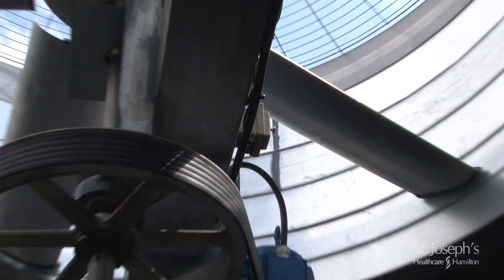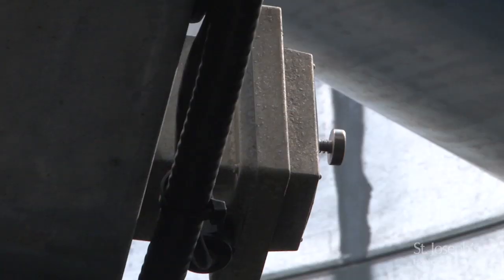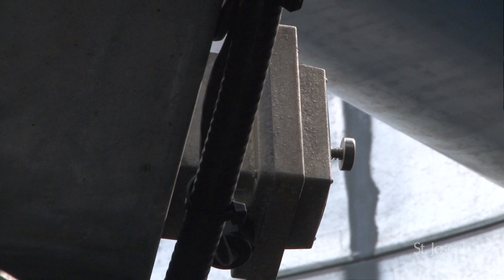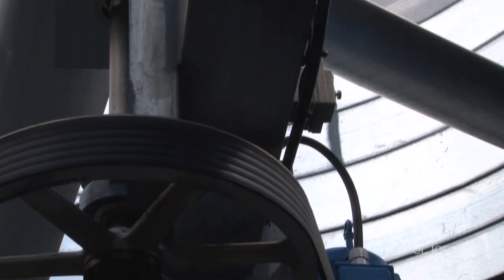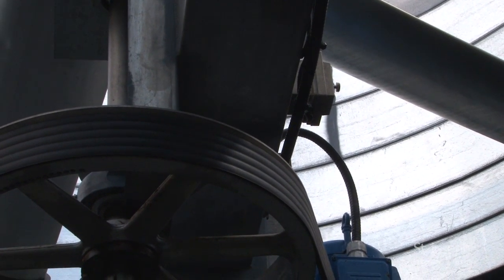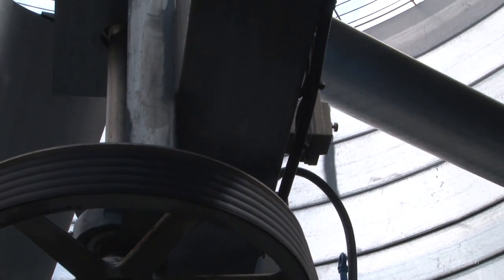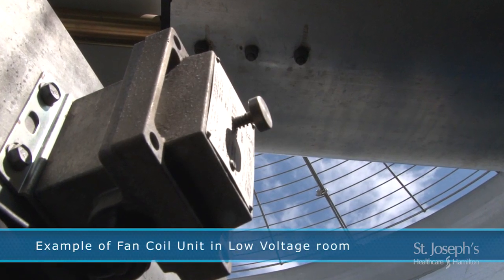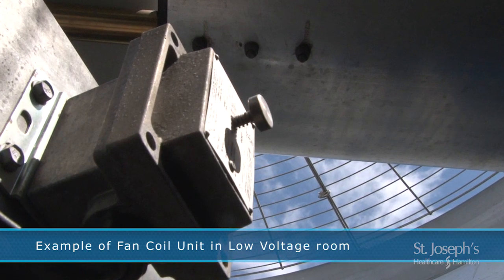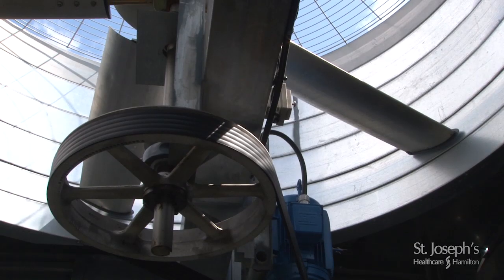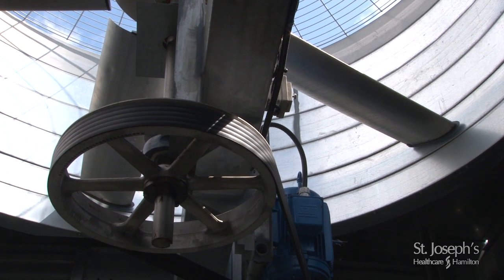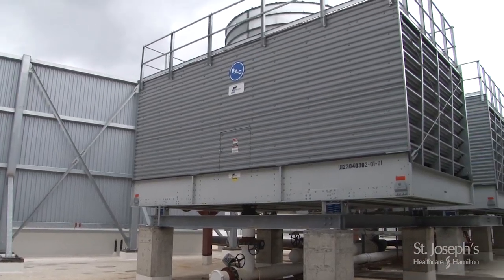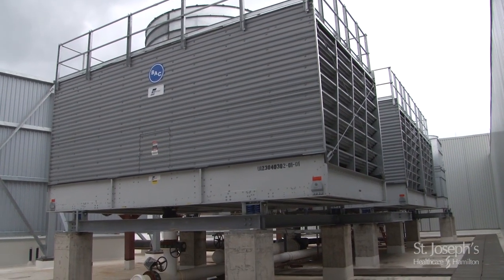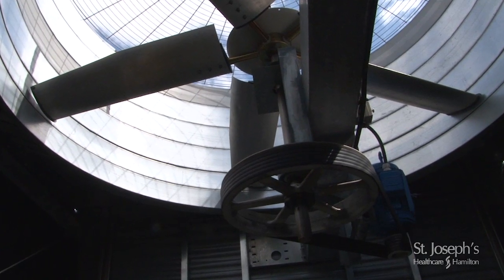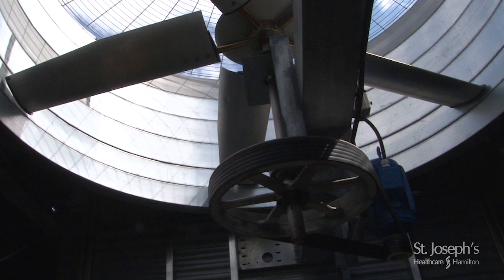Just slightly above the motor, that's your vibration cutout switch. That is to protect the fan. If something were ever to fail and you can't get it to start, you should be getting an error code back at your VFD. That error code would indicate that the vibration switch has tripped. Once you've reset that switch and you realize the fan is now running again, you haven't fixed the problem. All you've done is been able to get the tower to run again, and you need to start diagnosing why did that trip. What we would want to do is to start bringing the fan up at very slow increments.